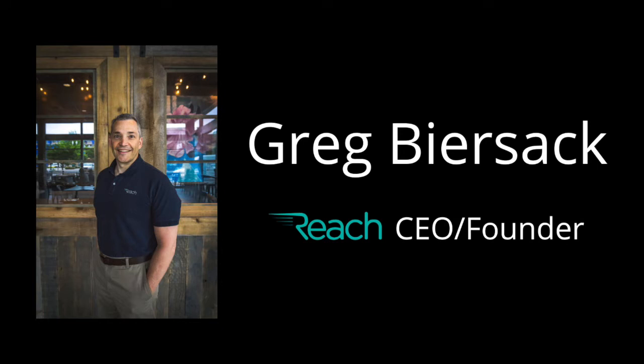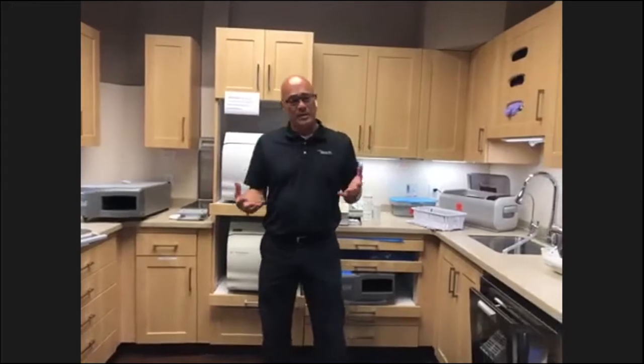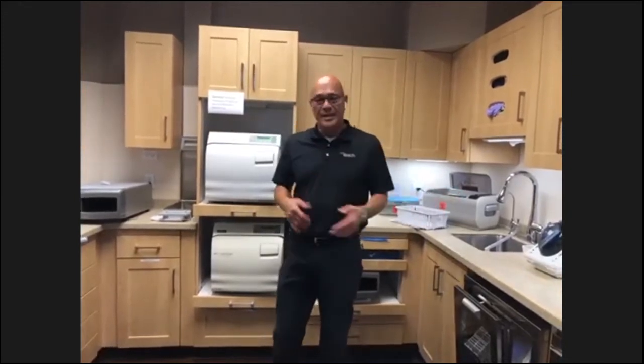The first one is, how often should you test your sterilizer? Okay, so for your sterilizer, you have spore tests, and you can do that in-house if you have the unit, an incubator, or you can send it out. The majority of people just send it out for third-party testing. That's done weekly.